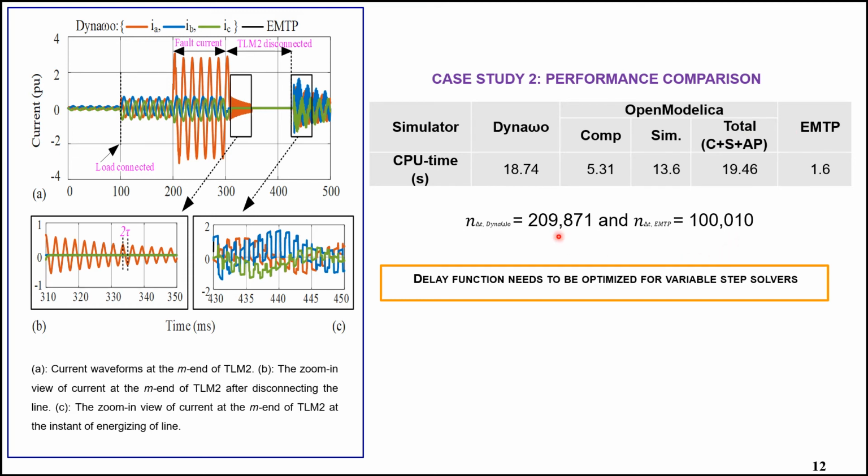I would like to draw your attention to the number of time steps in Dynaωo, which is twice that of EMTP for this simulation. The delay function needs to be optimized for the variable step solver to improve the efficiency in Dynaωo.